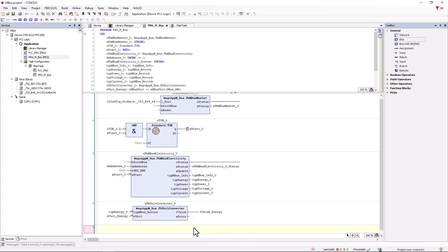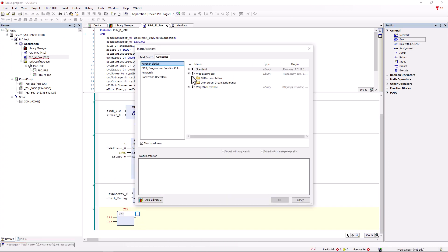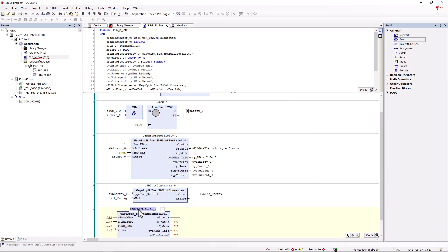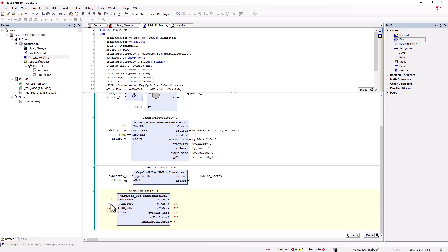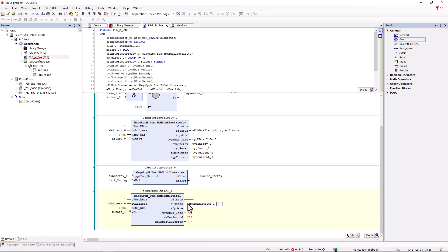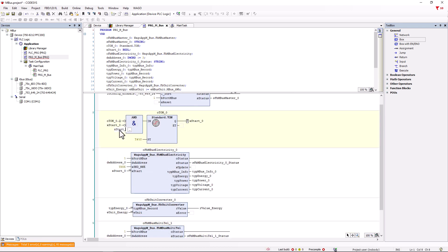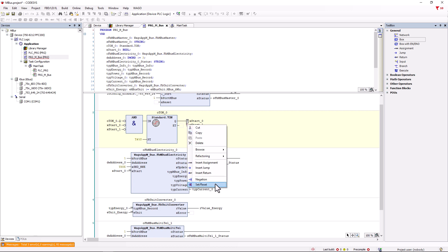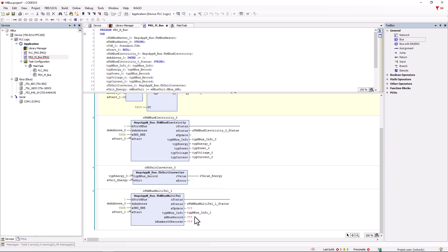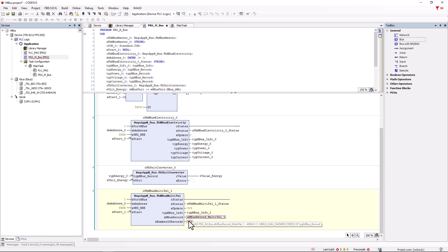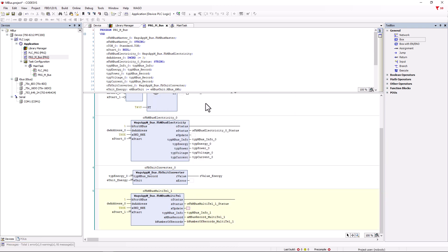So, new network, new box and we add the function block FB_MBUS_Multitel from the WAGO MBUS library and declare it. Accordingly, we create the addresses and declare variables for xStart and the outputs, s_status and type M-BUS info as before. The new xStart variable also arrives at the AND gate and the output of the timer module. At the aMBUS_record output, the entire dataset is now provided to us as an array and we assign and declare the variable aMBUS_record_Multitel1 for this. We also assign a variable to the B_number_of_records output which indicates how many values we can read out overall. When we log in and start the controller, at B_number_of_records we see that 32 values are available to us.